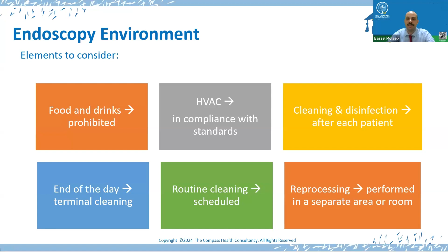With the exception of point of use cleaning, reprocessing of contaminated equipment should be performed in a separate area or room, not in the endoscopy procedure room. Now, talking more about the environment, let's address the water issue. Water hardness is an important element we need to be aware of. Hard water used in the final rinse in the AER cycle may cause deposits on the endoscope, and these deposits will act as a potential focus for soiling and recontamination of the endoscope. It may also seriously affect the optical system of the endoscope.